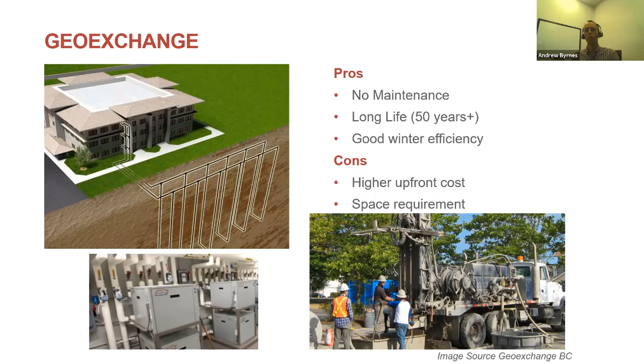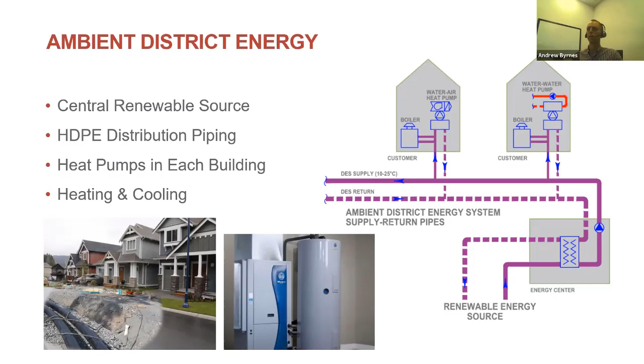One type of project we've been more involved with across BC and Canada is a district scale approach to heat pumps, energy recovery, and energy sharing. This is an example of what we call an ambient temperature district energy system, a way to cost effectively provide renewable low-grade heat to a variety of buildings within a campus. Each building can have a heat pump for heating or cooling as needed from a district energy system tied into a centralized Geoexchange, wastewater heat recovery, or other renewable energy source—distributing it widely at a district scale.